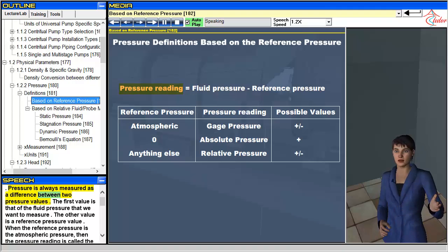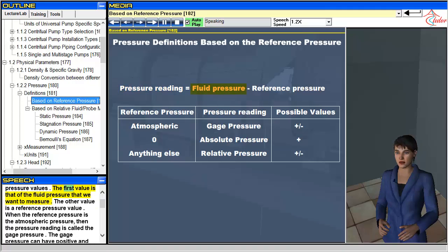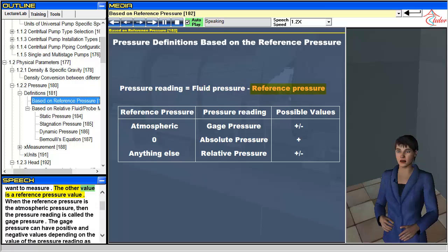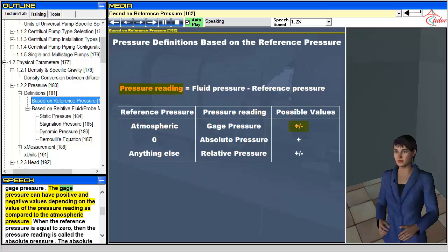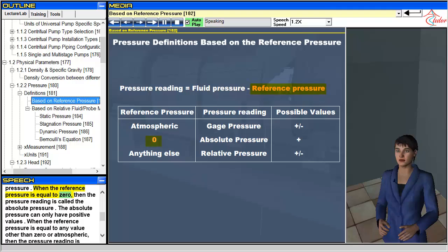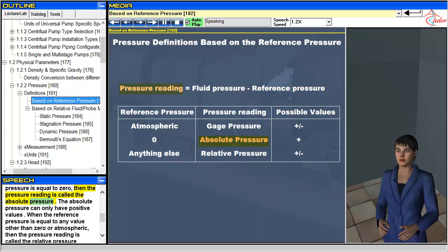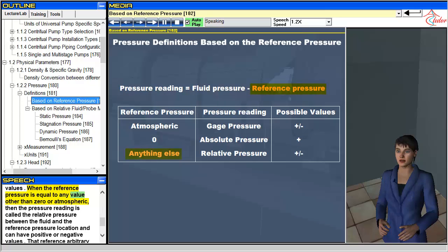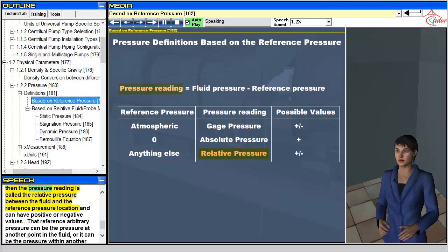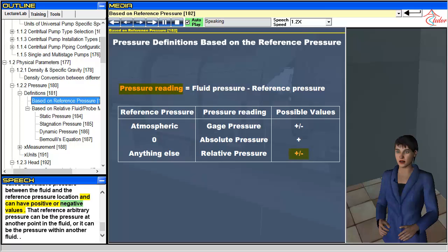Pressure is always measured as a difference between two pressure values. The first value is that of the fluid pressure we want to measure, and the other is a reference pressure. When the reference pressure is atmospheric pressure, the reading is called gauge pressure, which can be positive or negative. When the reference pressure is zero, the reading is called absolute pressure, which can only be positive. When the reference is any other value, the reading is called relative pressure, and can be positive or negative.